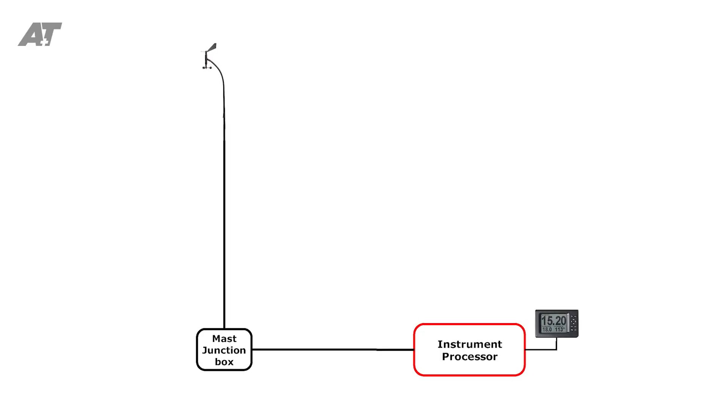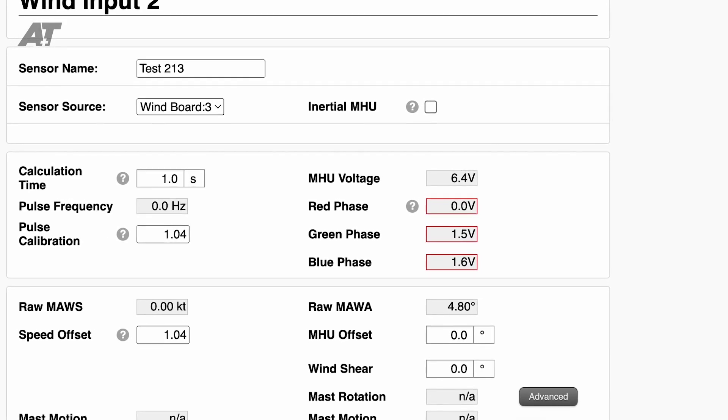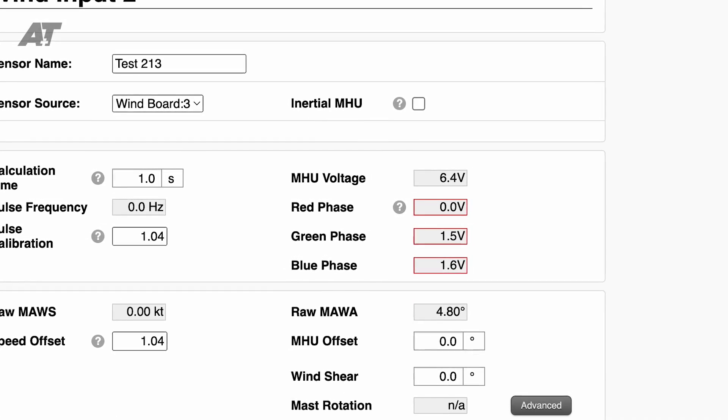If all of these are working and no data is shown on the processor, then the processor is faulty. If an A&T instrument processor is used, then these diagnostics are all provided on the web server.